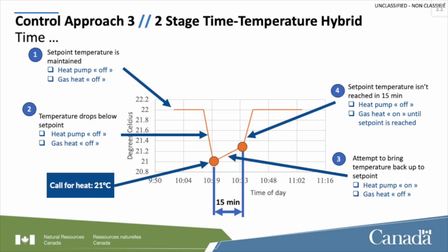So this one here is the time temperature approach, kind of the total hybrid approach. The temperature drops, the heat pump comes on, gives it the old college try, and if it can't satisfy it, we give it a time interval. In this case, we've given this thing 15 minutes to heat the house. At this point, it might be that we have too much of a gap to fill, or it might be too cold outside. Doesn't matter what it is, this thing needs a little help. The supplementary heating system kicks in, and away we go.